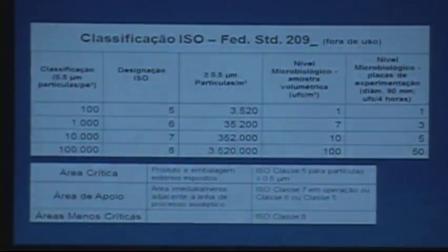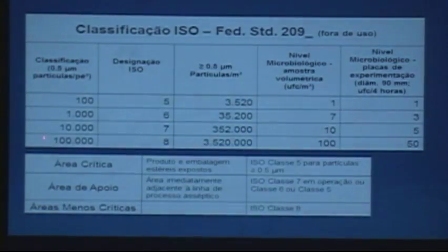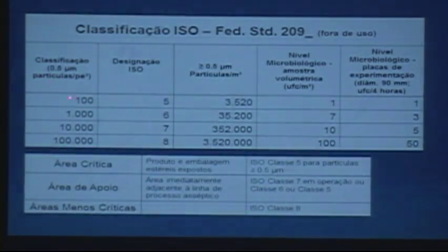Let's see if there's another comparison slide here. This comparison — class 100, 1000, 10,000, and 100,000 — was in use for many years. I have 31 years of cleanroom experience and for about 25 years I was speaking in terms of 100, 1000, 10,000, 100,000. This classification is from the Federal Standard 209 — the last version I used was 209E, and I also worked a lot with 209C.